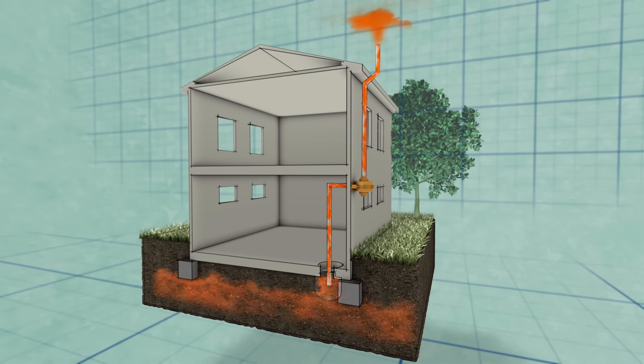This can be easy or complicated depending on the age of the house. At about 100 years old, this house likely has compacted dirt and soil underneath the slab rather than a gravel base. In a new home, the gravel base allows airflow so suction is easy to achieve across the entire slab. In an older house, compacted earth means we may not have enough pressure field extension — airflow beneath the slab — so we'll need to run tests to verify that.